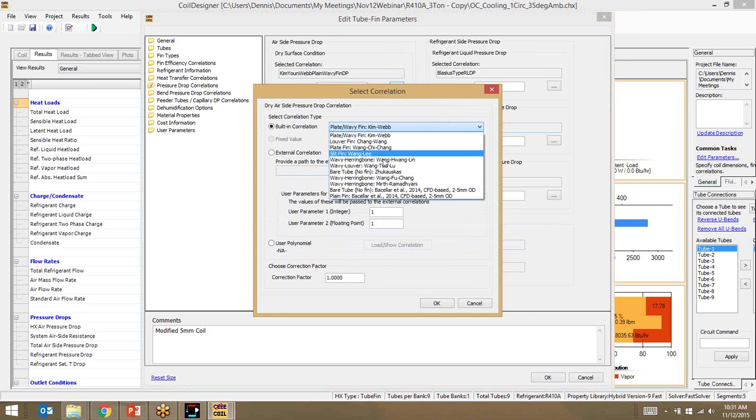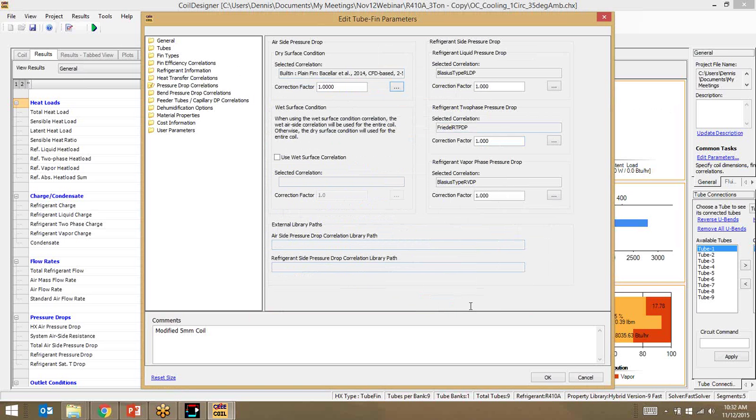And I'm going to do the same thing for pressure drop correlation on the air side. So this is the plain fin CFD-based correlation. So we have reasonable confidence in the fact that this correlation should predict our 5 millimeter outer diameter plate fin heat exchanger pretty well, because we have a whole lot of CFD data to back that up.